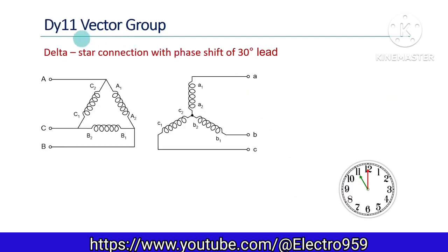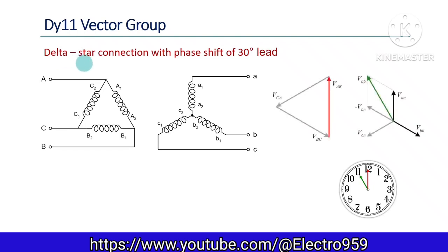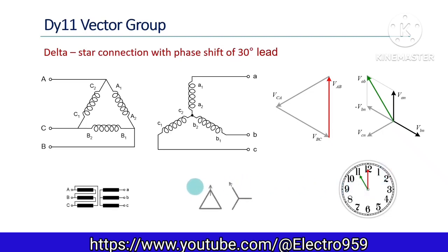The last one in this listing is the DY11 vector group. The primary is delta connected and the secondary is star connected. In the phasor diagram, the voltage induced in winding A of the secondary will be in phase with the primary line voltage. The line voltage VAB in the secondary is obtained by VA minus VB as shown. Finally, the line voltage is leading by 30 degrees from the corresponding primary voltage — the 11 o'clock position matches here also. The simplified connection diagram and displacement diagram are shown.